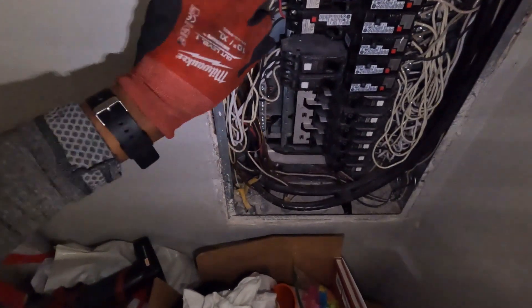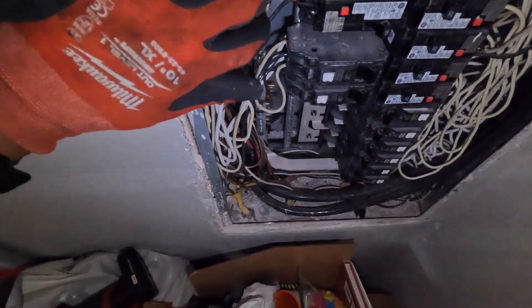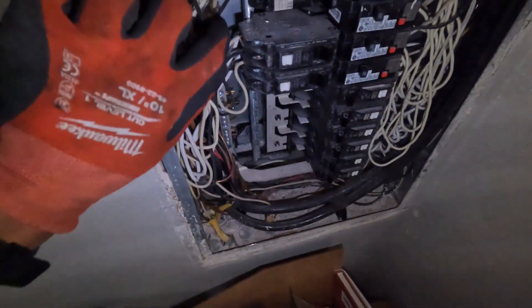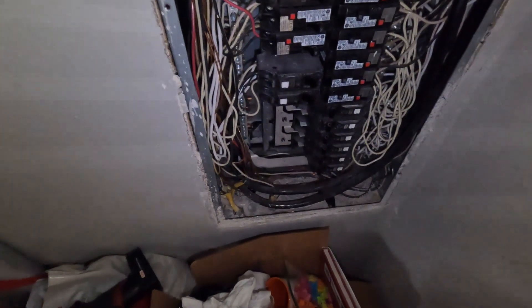There's two wires on there — two wires on that circuit. Look at that: they've got two wires under one breaker. They got a black and they got a red. I'm surprised this is not tripping also. Godly, that's crazy.